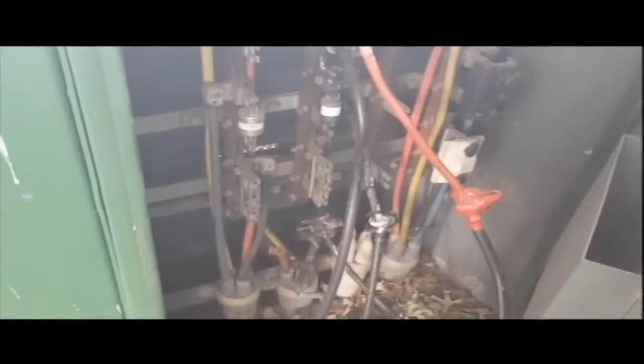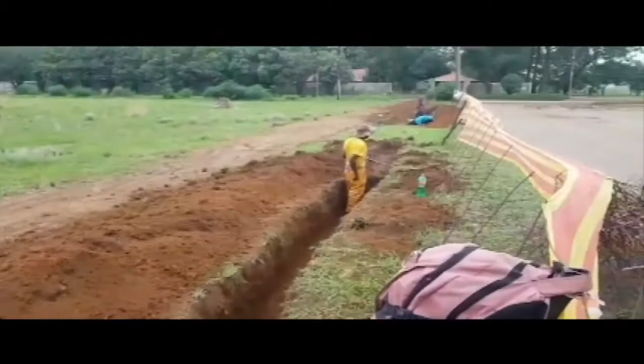One of the cables is a 2.7 kilometer cable ring, and it had more than 12 cable damages. So that meant we had to do 12 joints. And like in your hose pipe, every joint is your weakest link. At some stage, it's gonna explode. So the short-term solution that could be done was to reconfigure the network, do the backfeeding from different points which were still live. At that time, I think it was more than 70% of Three Rivers being off. So it was brought back.